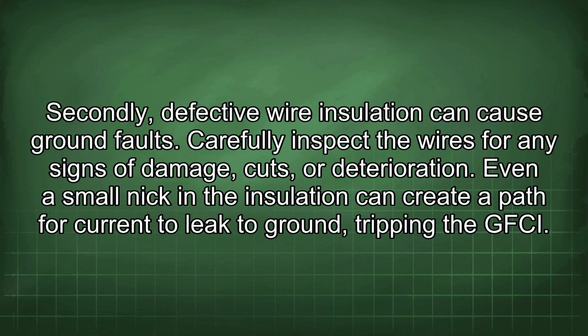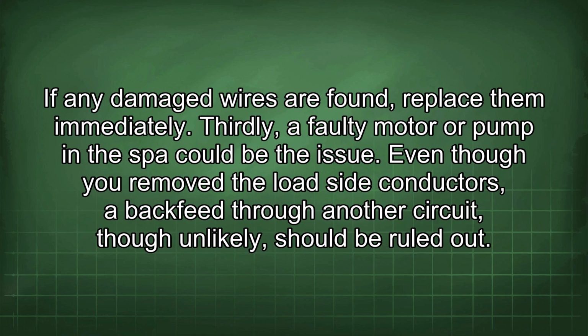Secondly, defective wire insulation can cause ground faults. Carefully inspect the wires for any signs of damage, cuts, or deterioration. Even a small nick in the insulation can create a path for current to leak to ground, tripping the GFCI. If any damaged wires are found, replace them immediately.